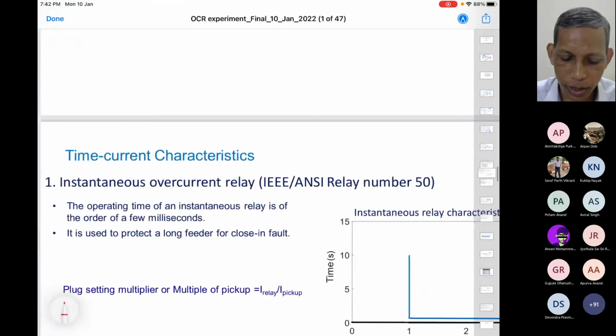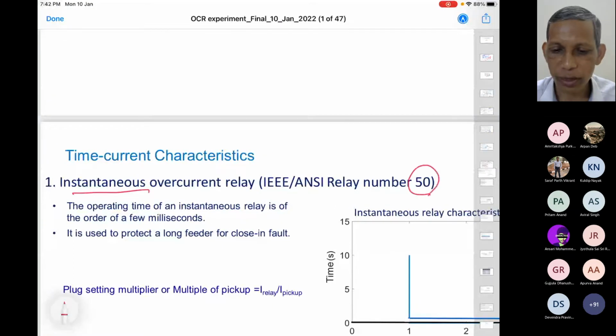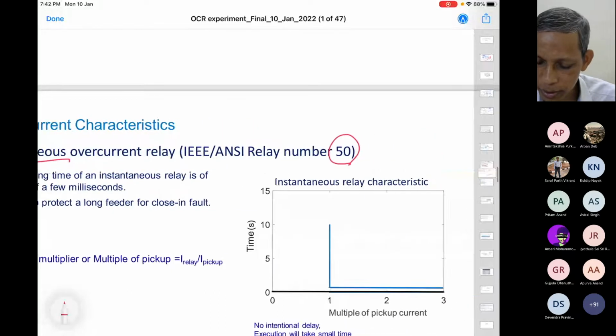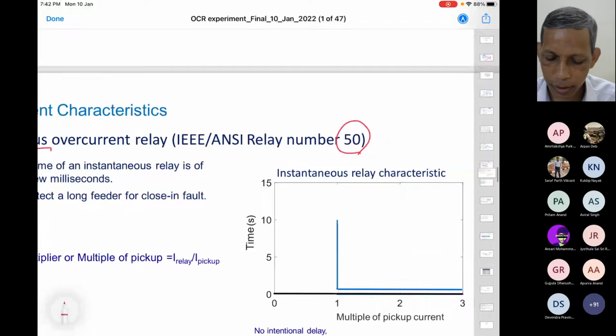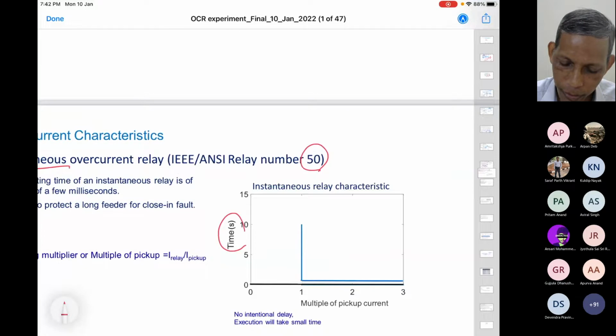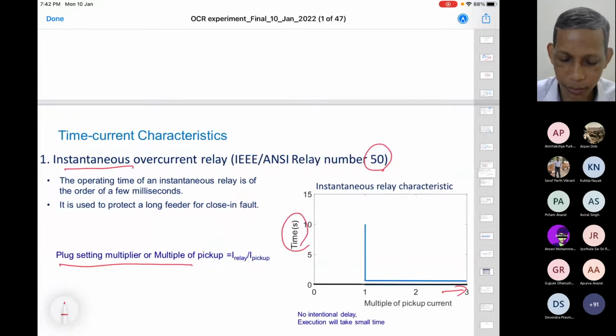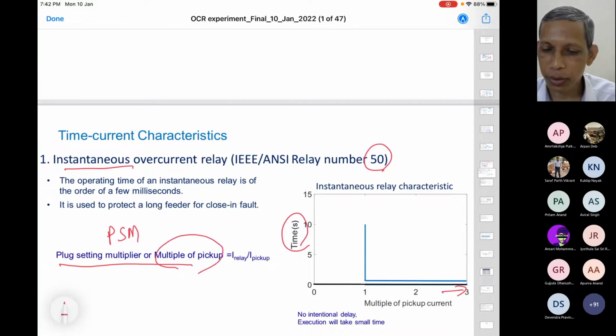So when it is instantaneous, we call it number 50, no delay, and the characteristic becomes like this. The y-axis is time, and the x-axis is the current as a multiple of pickup current. So consider the plug setting multiplier, PSM. Remember PSM, plug setting multiplier, or multiple of pickup: how many times the pickup? It is the relay current divided by this I pickup. This pickup is nothing but the setting.